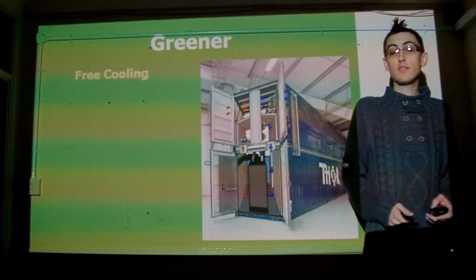Power usage effectiveness, or PUE, is a metric of data center efficiency. Most data centers achieve a PUE of around 2.5. That means that for every 1 watt going directly to computing equipment, another 1.5 watts are required to power cooling systems and other overheads.